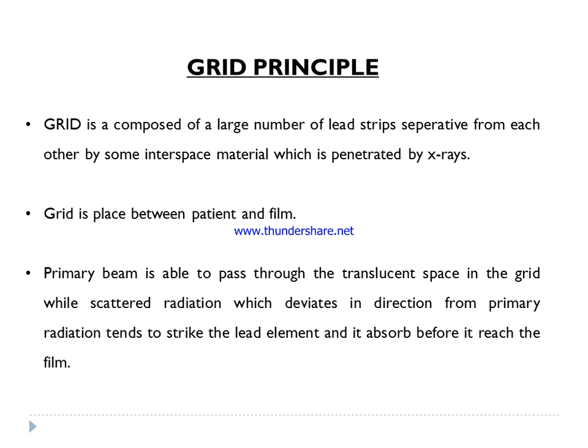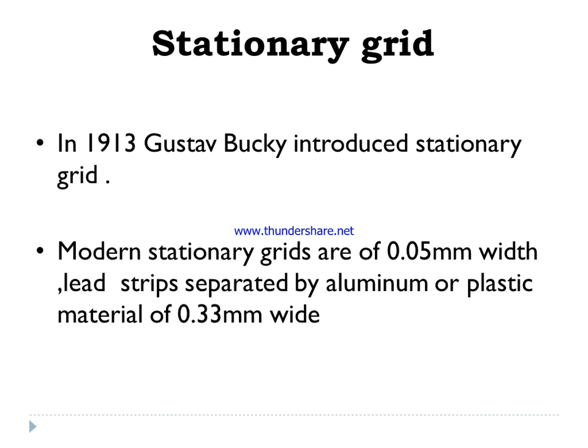In the case of scattered radiation, which deviates in direction from the primary radiation, it strikes the lead elements and is absorbed before reaching the film. This is a stationary grid. In 1913, Dr. Gustav Bucky introduced the stationary grid. Modern grids have lead strips of 0.05 mm width, separated by interspace materials. The interspace material used is aluminum or plastic, which is 0.3 mm wide.